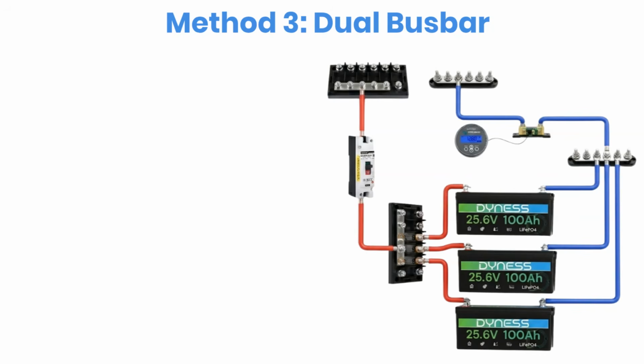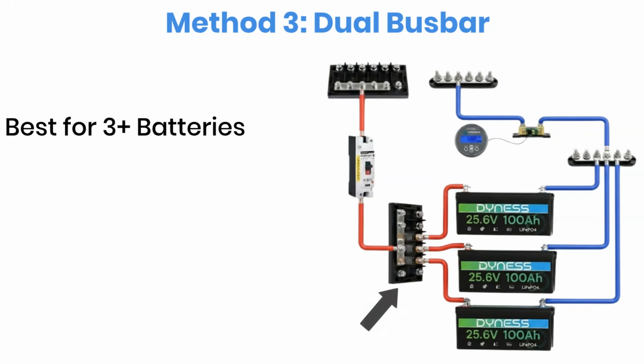The third method is designed for larger battery banks and works especially well when you have more than 3 batteries connected in parallel. In this setup, all of the batteries connect to a dedicated battery busbar first. Then, a single heavy-duty cable connects that battery busbar to the main system busbar. This keeps the wiring much cleaner, makes future upgrades easier, and gives you plenty of room if you decide to expand your battery bank later.